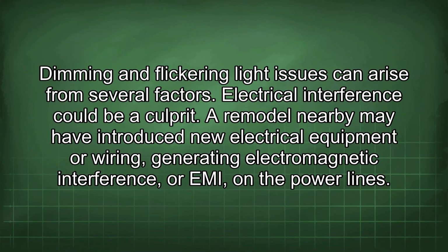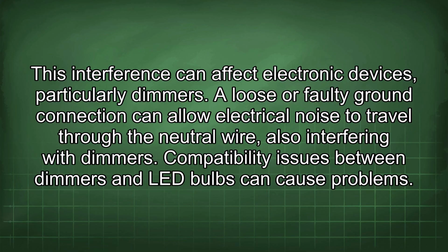Dimming and flickering light issues can arise from several factors. Electrical interference could be a culprit. A remodel nearby may have introduced new electrical equipment or wiring, generating electromagnetic interference, or EMI, on the power lines. This interference can affect electronic devices, particularly dimmers.